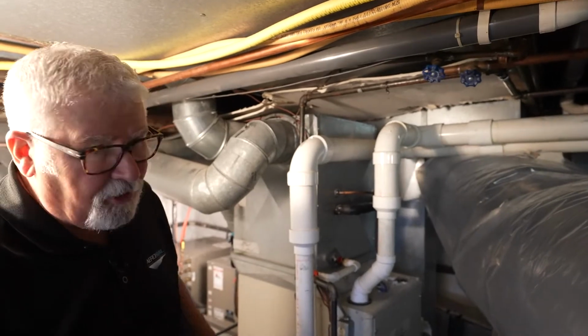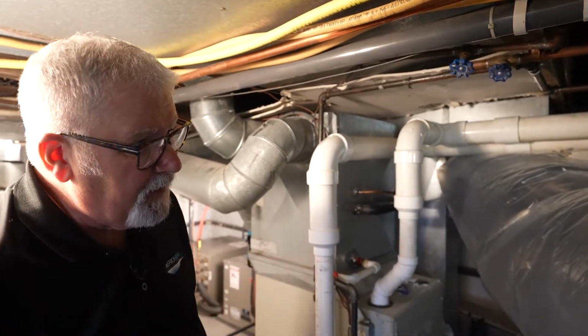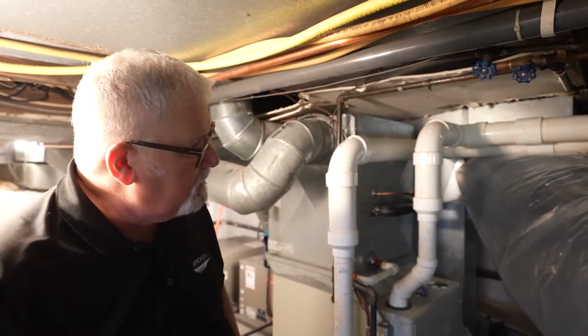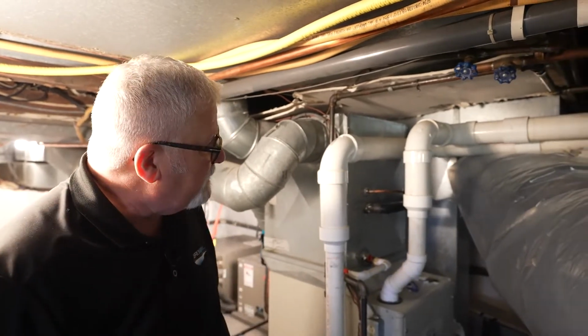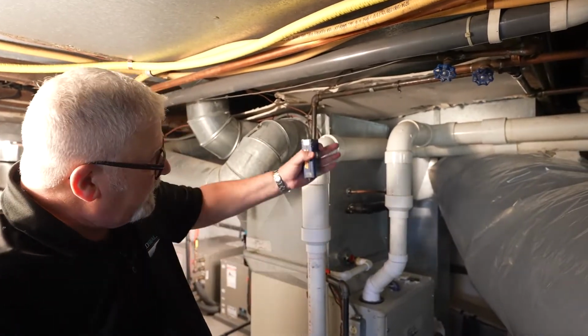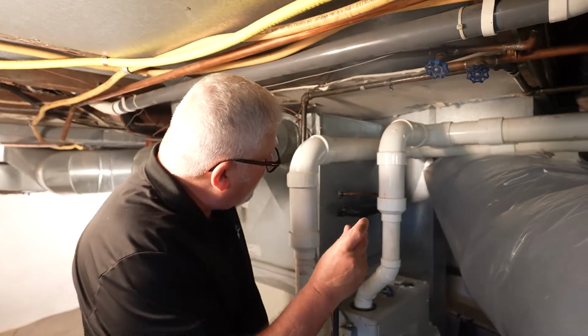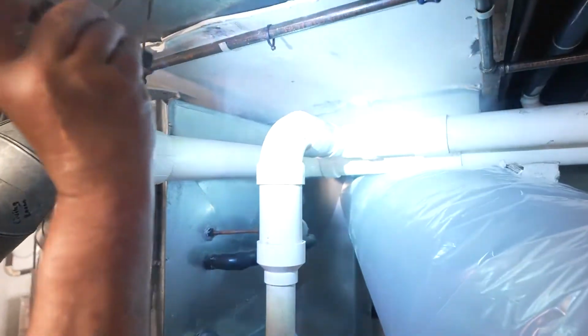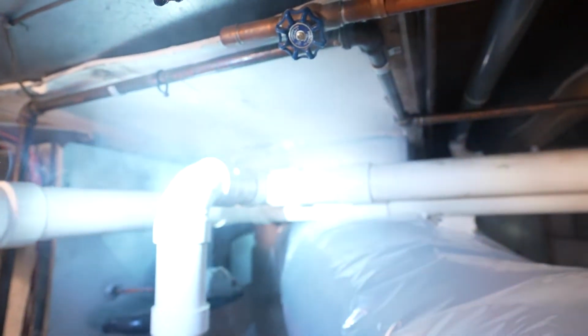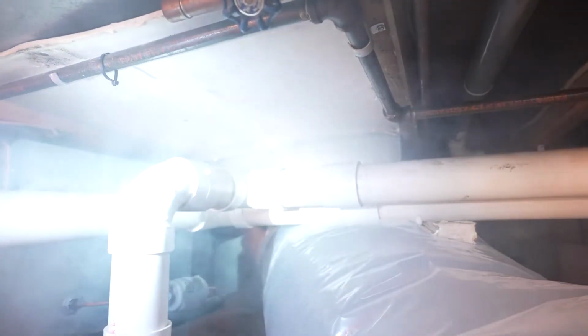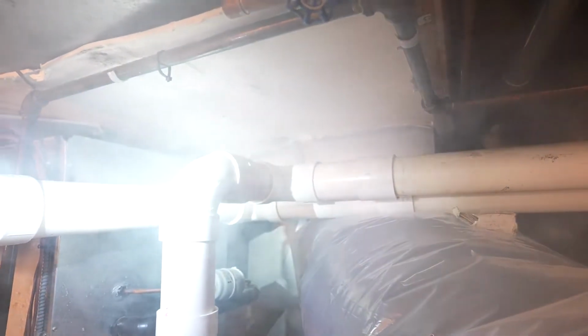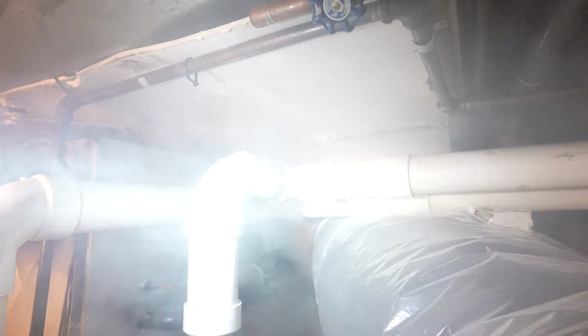To make sure we can find other spots that may be leaking, we're going to fog the system using a little fogger at the back. As the fog comes through, if there's holes, oh my God, look at this right here - can you see that fog? There's something bad wrong right there. We're going to have to pull this sheetrock down and see what's really going on, and yeah, that's got a big hole back in there somewhere. If I tried to Aeroseal this right now without finding this ahead of time, we would have had a huge mess down here.